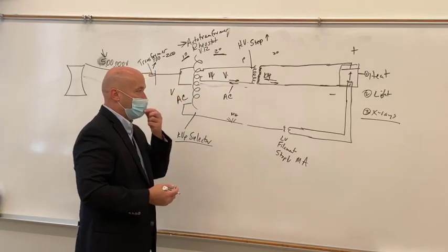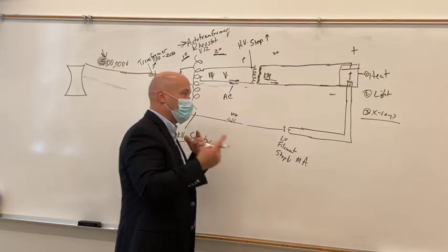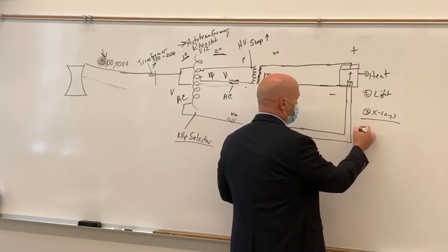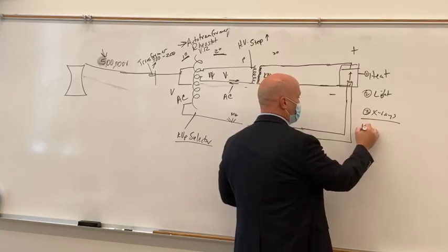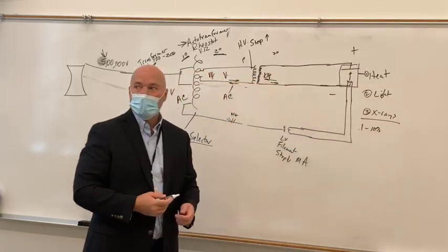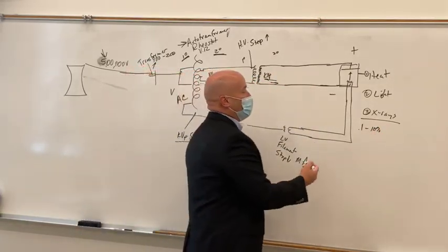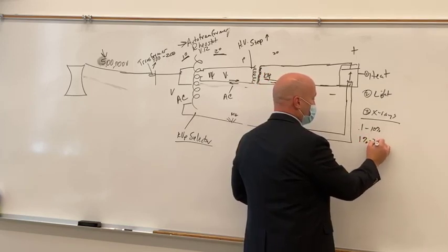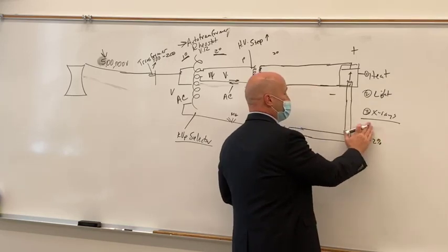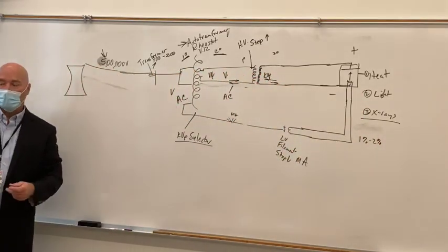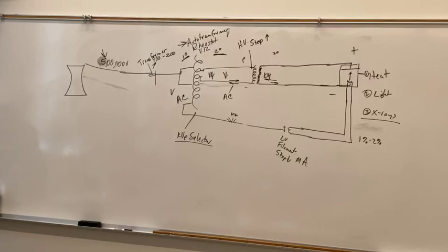The conversion rate of the electricity to X-rays is anywhere from, say, 0.1 to 10%, depending on a lot of different things. Okay, so very, very inefficient, and most likely, most of those are going to occur right around 1 to 2%. Are going to actually convert from electricity to X-rays. Very, very low percentage actually become X-rays.